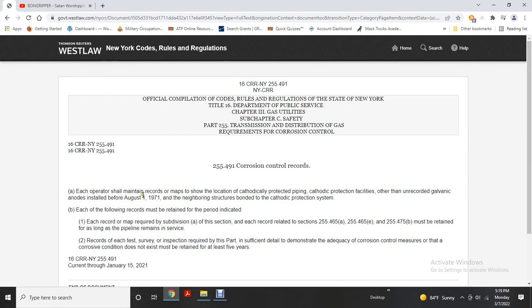Corrosion control records: each operator shall maintain records pertaining to the location of cathodic protection pipe, the cathodic protection system, and other unrecorded galvanic anodes installed before August 1st, 1971, and neighboring structures bonded to the cathodic protection system. Each of the following records must be retained as specified: each record of maps required by subdivision section, each record related to Sections 255.465(a), 465(e), and 475(b) must be retained as long as the pipeline remains in service. Each test, survey, and inspection required by this part, and details regarding the adequacy of corrosion control measures and corrosion conditions found, must be retained for at least the last five years.